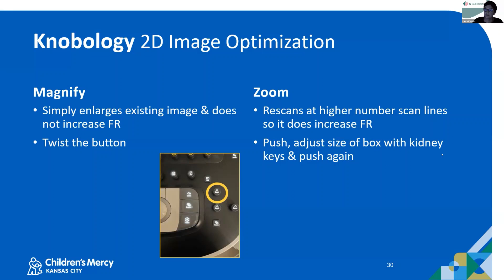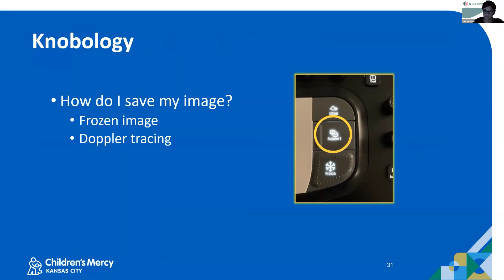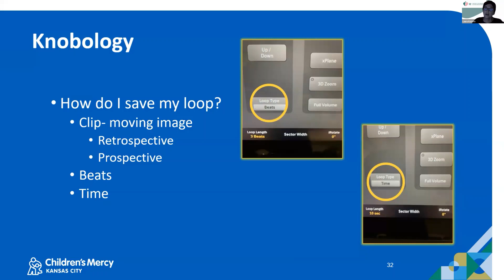So I've got my optimized depth, I have nice gain, my 2D settings look good, my sector width is great. So I want to save an image. How am I going to do that? If you're going to save just a frozen image or a Doppler tracing, you're just going to hit freeze and hit acquire. But I need to save a loop now, or a moving clip. You can either save an image based on beats or time. It will acquire 3 cardiac cycles if you set it to 3 beats, or 10 seconds if you want to do a nice sweep. You can acquire retrospectively, which means you hit the acquire button and it's going to take the prior 3 beats, or prospectively, you hit acquire and it's going to take the next 3 beats. And this is just driven by your lab and their protocol and how they like to do things.